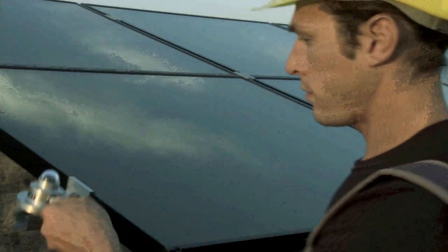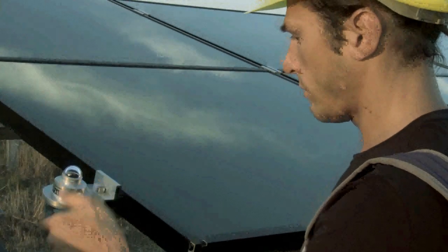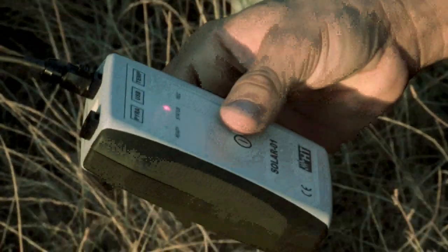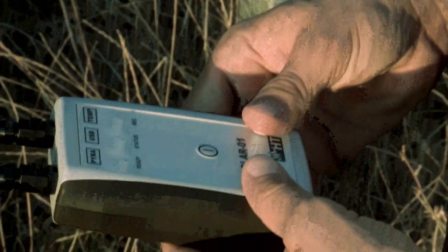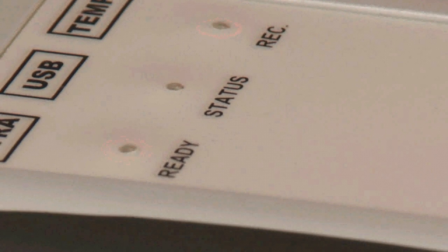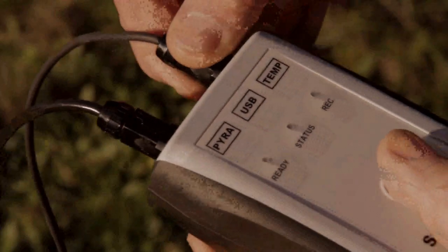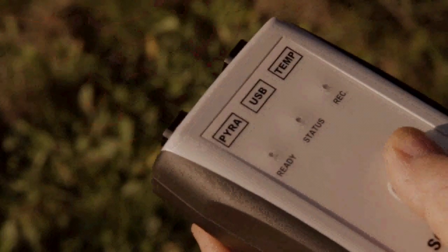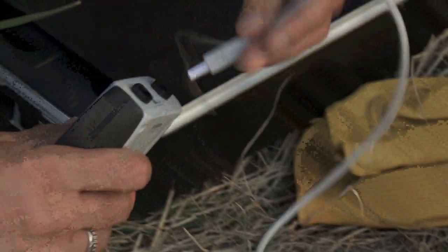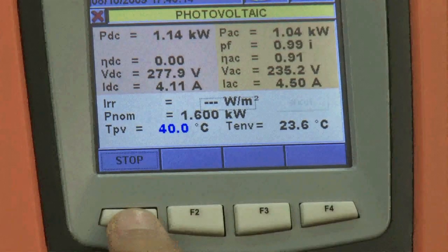The temperature of the photovoltaic modules is detected by means of a probe, which is positioned on the lower surface of the modules. Irradiation is measured by a precision transducer. Environmental temperature is detected directly by the remote unit. When the ready LED on the remote unit is on, at least one valid irradiation value has been acquired while measuring. Then you may connect the remote unit to SOLAR300N again, stop recording and wait for the main unit to download all data from the memory on the remote unit.